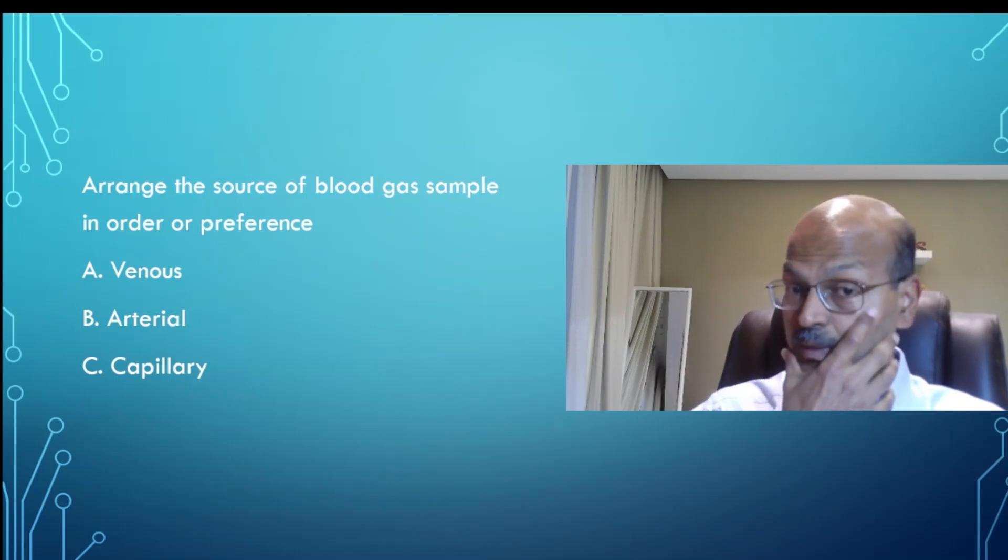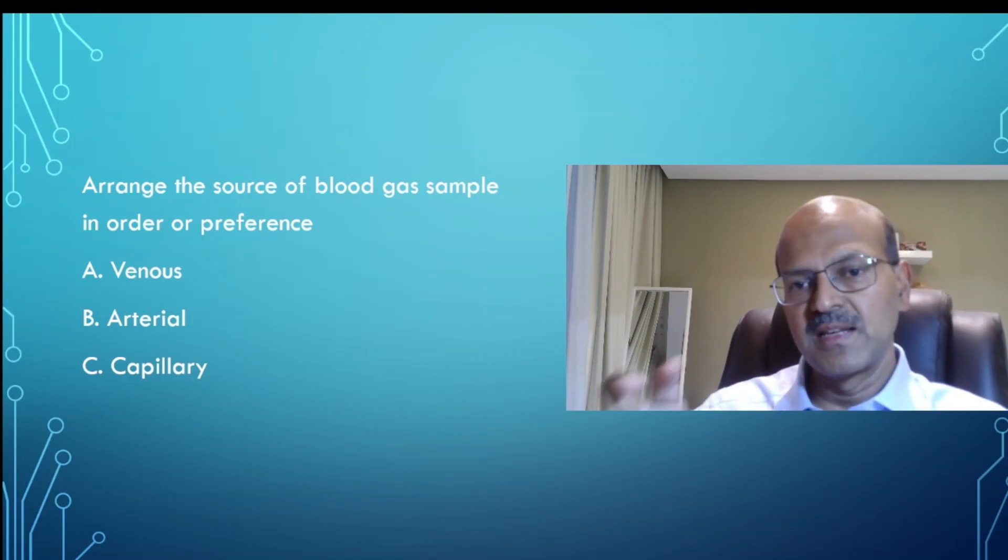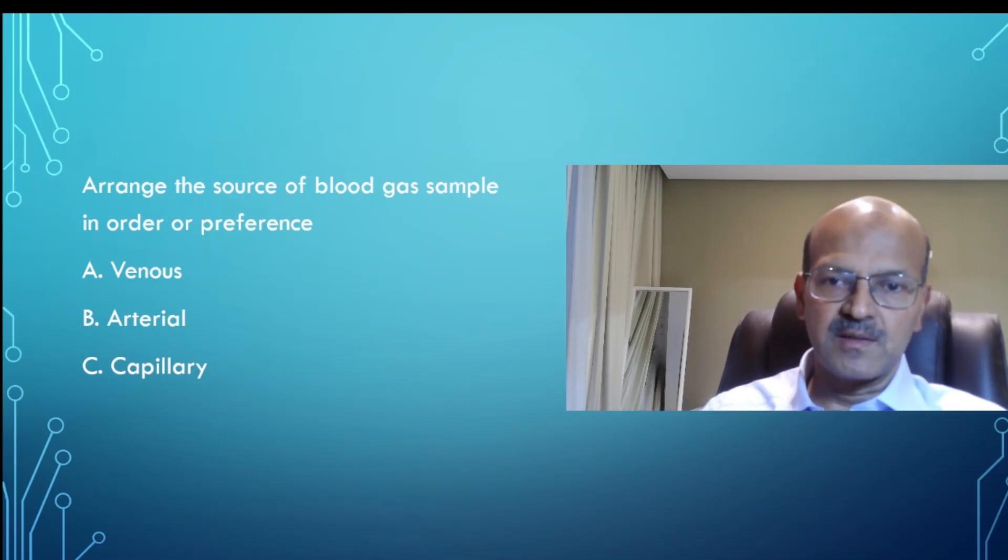Another important point about blood gas in babies on therapeutic hypothermia is to reset the machine setting to the temperature of the sample. So like 33 to 34 degrees or whatever you're keeping because the temperature affects the interpretation of the gas, how the blood gas machine runs it. The standard is fixed at 37 degrees, so you have to change it in the babies who are on cooling.